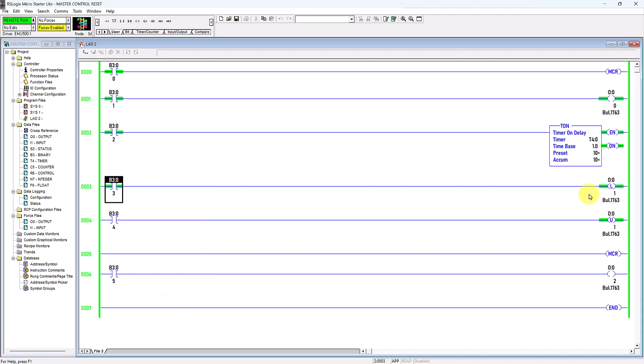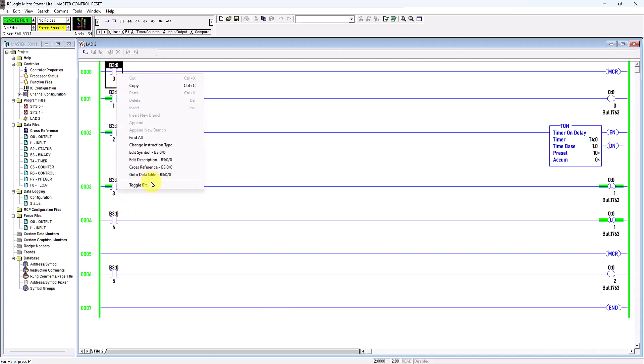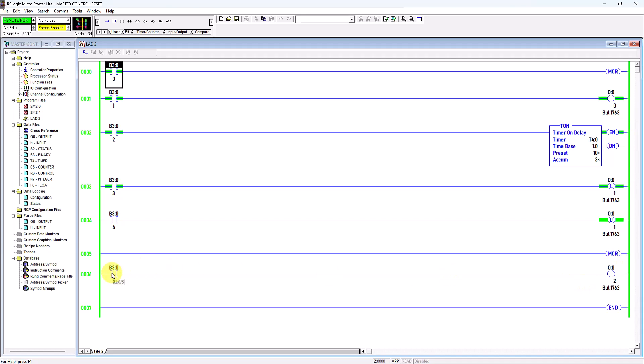If I de-energize the MCR, all non-retentive outputs such as the output coil and the timer will be de-energized. However, it will have no effect on retentive outputs such as the latch/unlatch virtual output coil. You can see it turns off the non-retentive output coil, but cannot de-energize the retentive output. For the rung outside the control zone, it has no effect whether MCR is energized or de-energized. That's it, thanks.